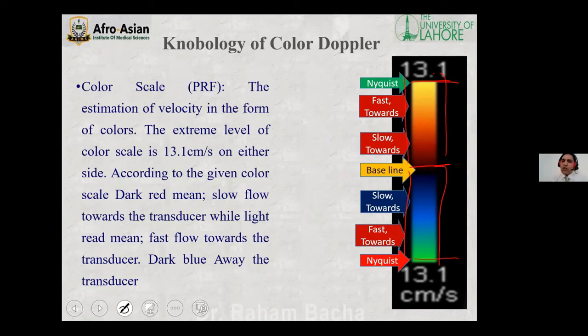You can change it by increasing PRF, by increasing the scale. So in this example, it can measure any velocity in the color box up to 13 centimeters per second, but any velocity above 13 centimeters per second could not be measured with this, and that will alias. We will discuss it later on.